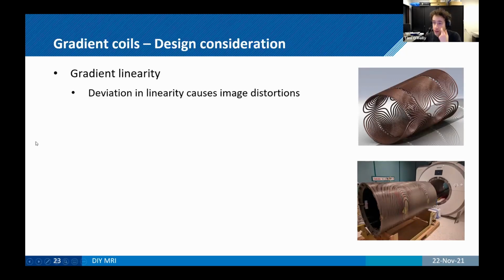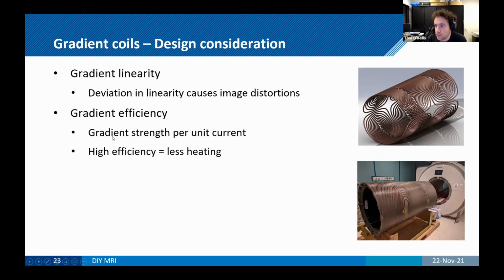So first and foremost is gradient linearity. So if your gradient is not perfectly linear, you're going to have distortions in your images. Commercial systems also have gradient nonlinearities. They just correct for them before they show you, but they definitely do have them. Gradient efficiency, which is how strong are your gradients per unit current that you're putting through. And high efficiency means less heating because of, again, I squared R. And as I mentioned in the question before, the gradients do start to contribute heat and temperature drift. So this is something to be careful with.